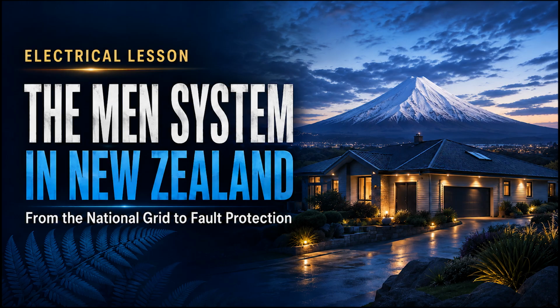The neutral is earthed at the transformer, at points along the distribution network, and at connected installations. These multiple connections help hold the distribution neutral close to earth potential and provide parallel connections to the general mass of Earth. Multiple earthing can reduce the overall impedance to Earth and helps control system voltages relative to Earth. It can also provide some resilience when one earth connection is poor.